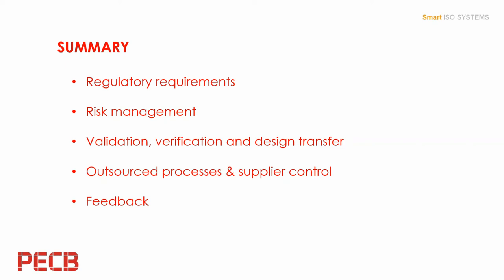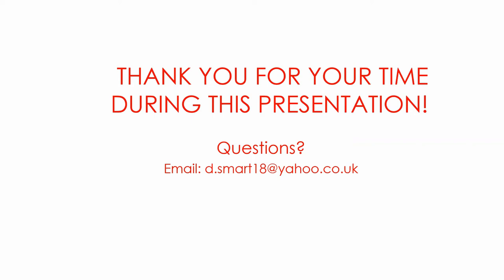And the final point is feedback. The draft requires you to monitor and measure the performance of your quality management system, not only during production, but also post-market activities. You also have to incorporate those activities as part of your risk management process. The linkage between the different clauses within the standard has been improved. Now everything is more interconnected, more joined up. You have to have systems in place that allow you to demonstrate conformance across the requirements. It's a much more integrated approach.